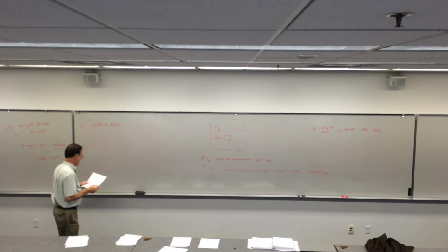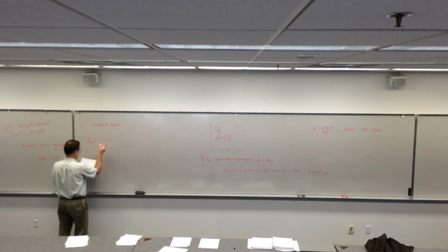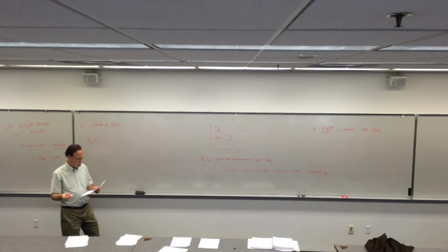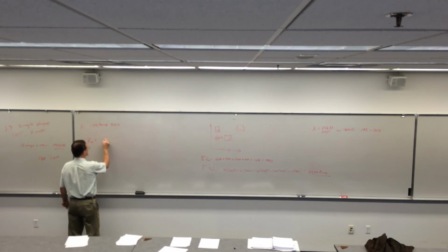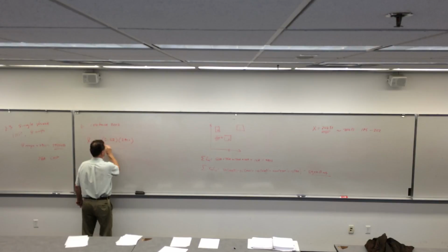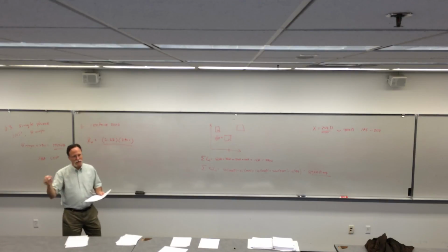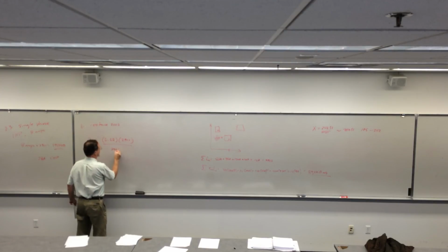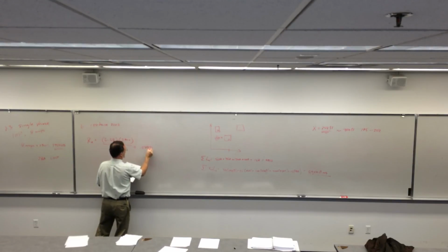All right. So what is my allowable resistance in my line? I want to have a 2% drop. That's typically what you do, a 2% or less drop. What's the service? 240 volts. So I have 0.02, which is 2% times 240 volts, divided by the distance. I'm 100 feet away from the load pole, so twice the distance, because it's a circuit that goes there and back, is 200 feet. So that gives me 0.024 ohms.